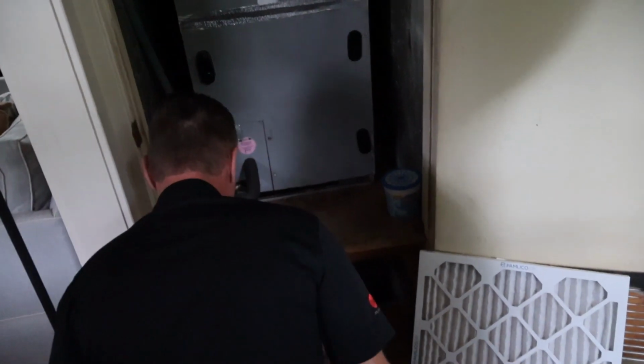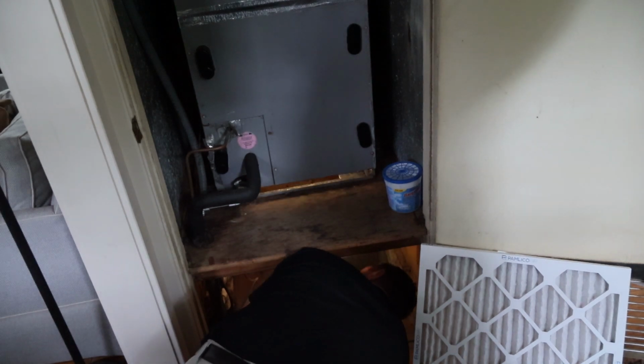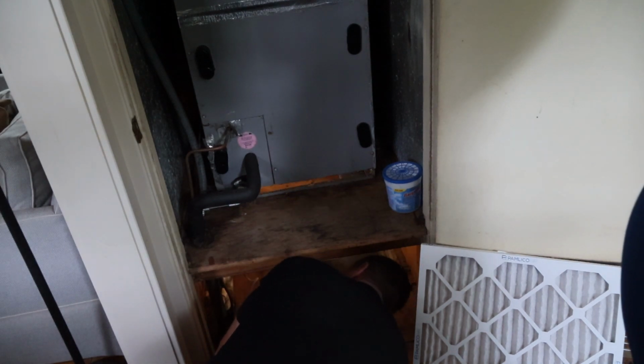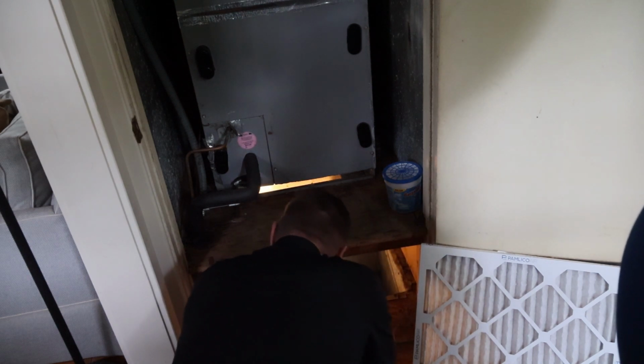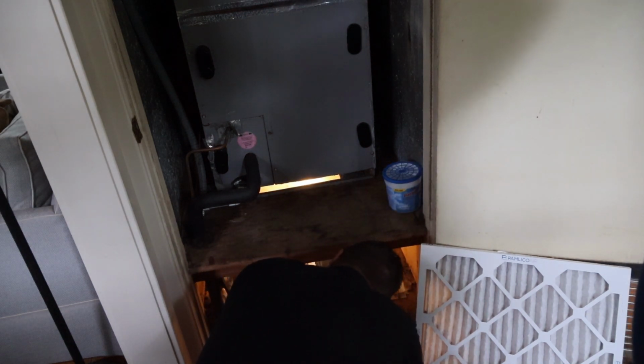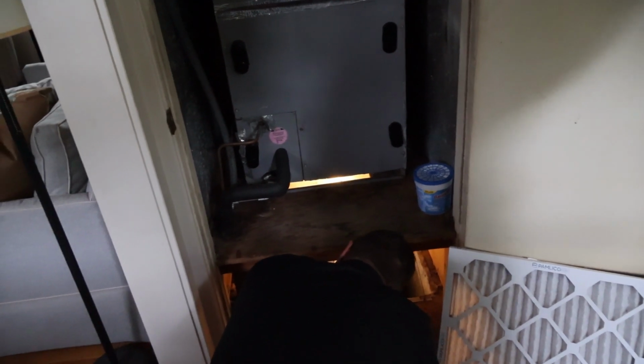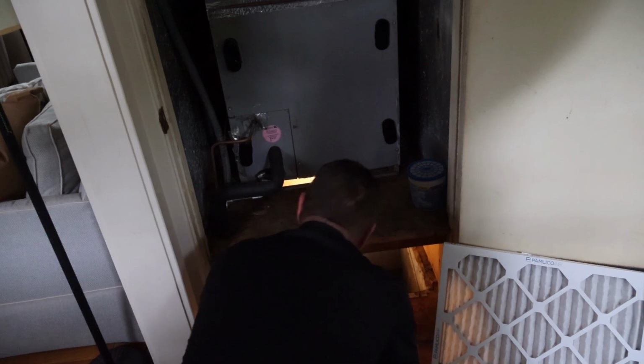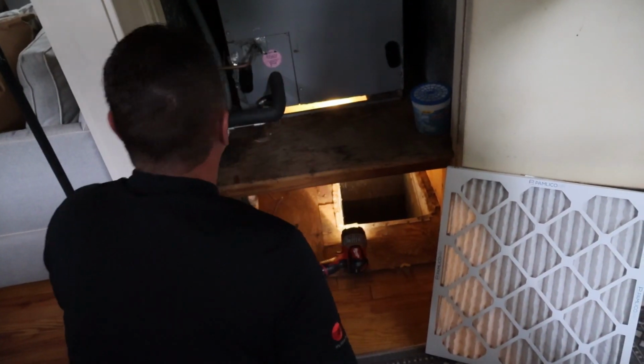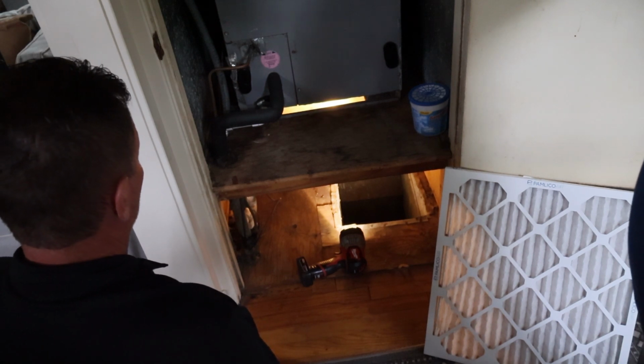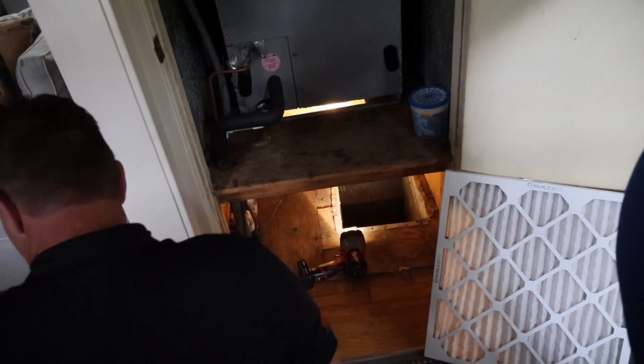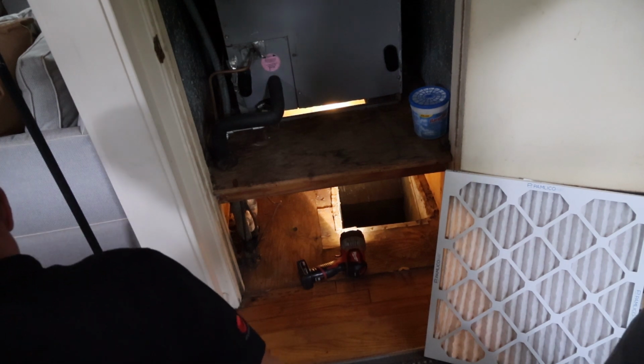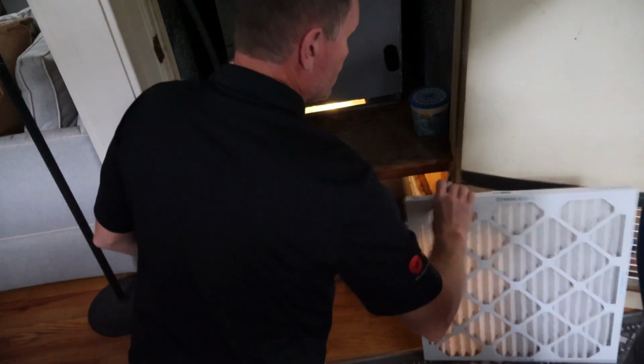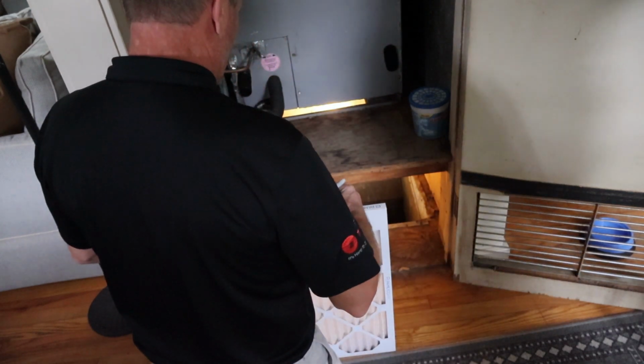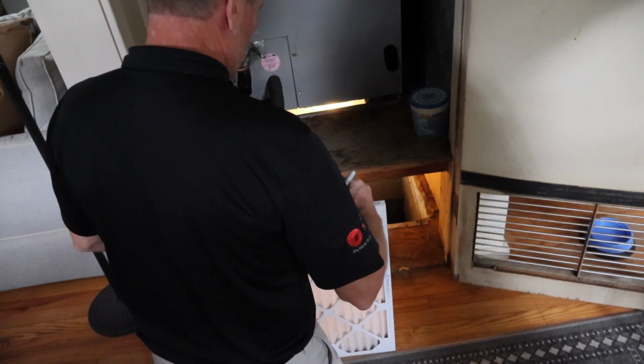It also has another filter in the hallway, so if you only see one that maybe is in the air handler, it's not a bad idea to look around to see if you see another grill somewhere. This one's actually in the floor down a hallway, so make sure you get all the filters changed and get them all dated as well. If a customer happens to see a dirty filter and it's not dated, it's going to feel like it hadn't been replaced. But with your date and even your initials, if you choose to, that will ensure that does not take place. And that's what Dave's doing now. Dave is dating it.